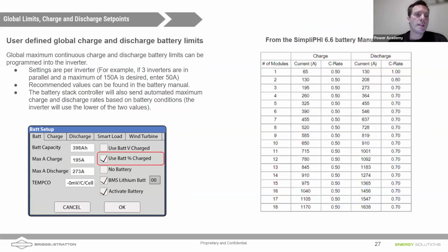Once we've got the battery communicating with the inverter, some of the values will automatically be set, and some you can set manually. So the battery capacity should show up automatically. The maximum charge amperage for a single stack I've got programmed in. You can adjust this. This is a global charge rate limit, so it won't go faster than this, and this includes all forms of charging. So if you've got solar charging at the same time as maybe grid charging or generator charging, the inverter will make sure not to exceed this maximum value.